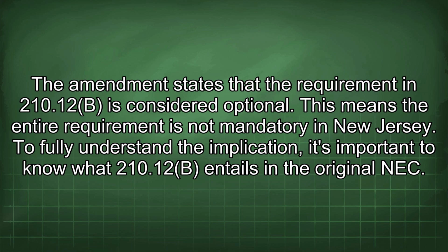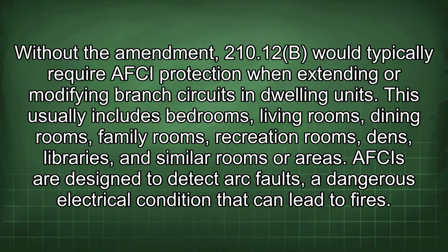To fully understand the implication, it's important to know what 210.12(B) entails in the original NEC. Without the amendment, 210.12(B) would typically require AFCI protection when extending or modifying branch circuits in dwelling units. This usually includes bedrooms, living rooms, dining rooms, family rooms, recreation rooms, dens, libraries, and similar rooms or areas.